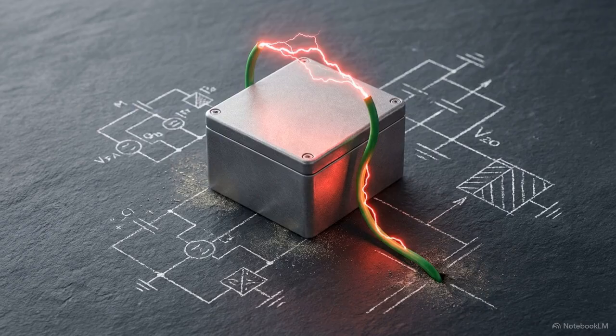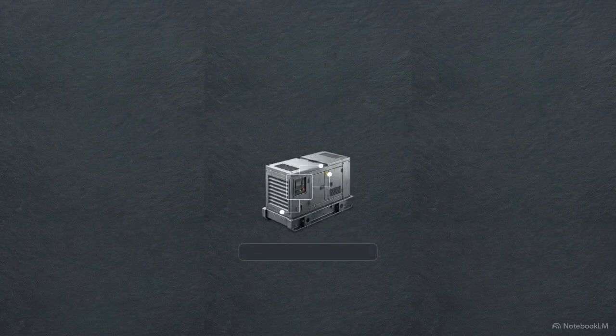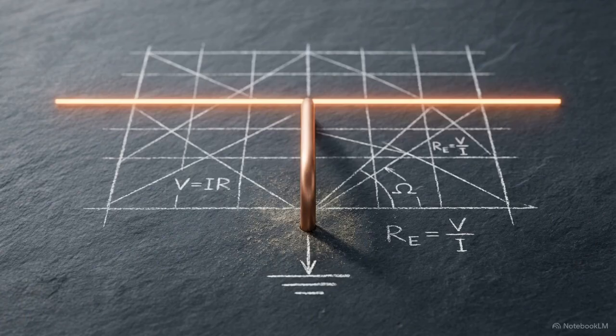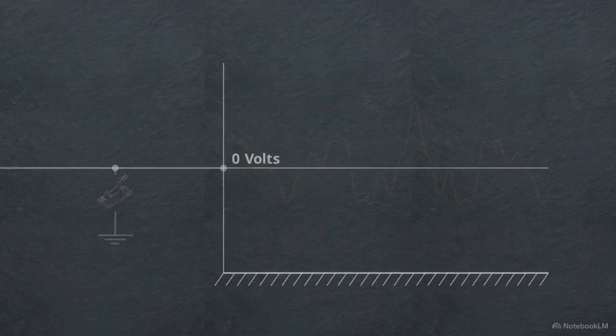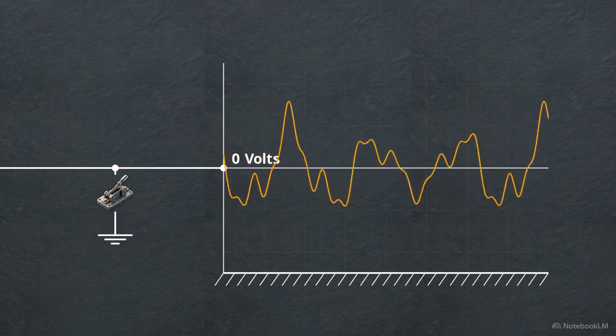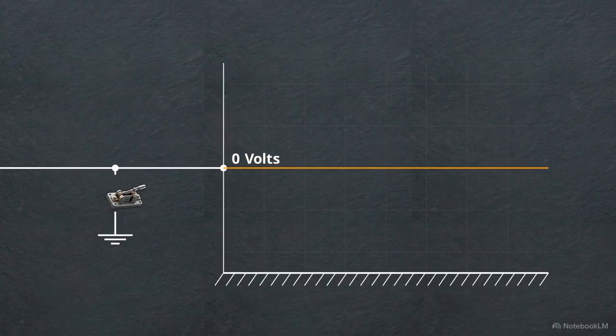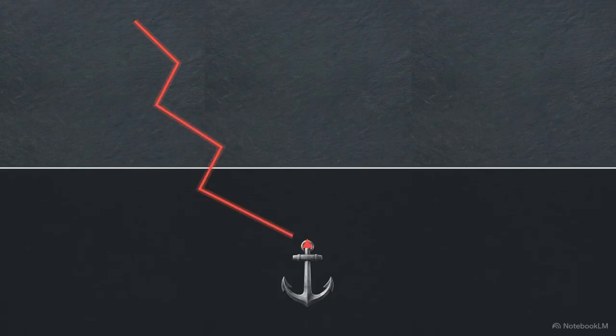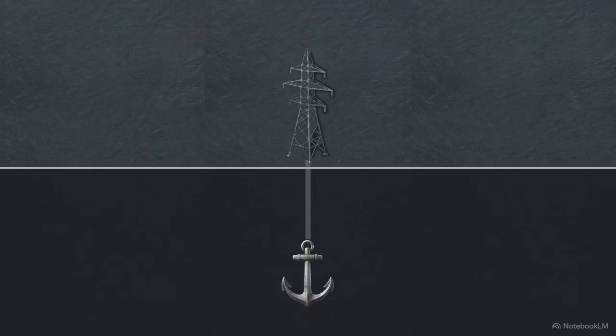The first primary objective of these connections is operational safety. By providing a dedicated, low-resistance route, we ensure that any hazardous rogue energy has an immediate path to exit the equipment, rather than discharging through surrounding materials. The second primary objective is source outcome stability. By connecting the source neutral directly to the ground, we actively stabilize the system's neutral voltage, locking it to a value very near zero. A properly engineered ground acts as the system's physical anchor. It provides both an emergency escape route for excess electrical energy and a fixed zero-point reference to ensure stable power delivery.